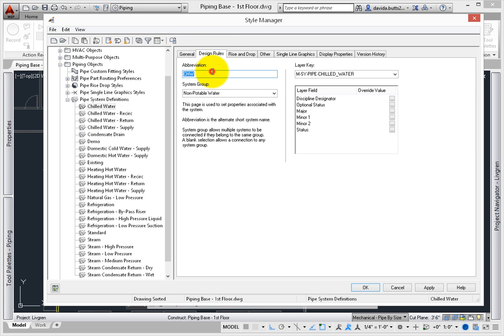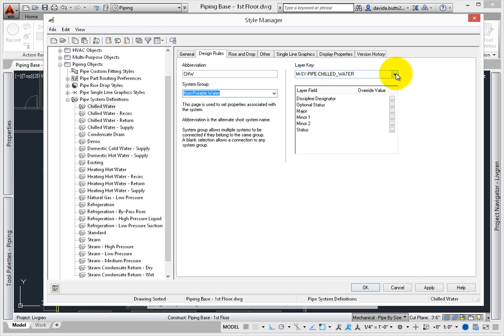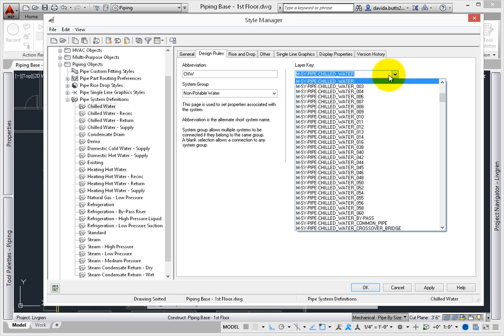Design rules set the abbreviation and system group. The system group prevents items from dissimilar systems from being connected together. Design rules also includes one of the more important settings – the layer. Autodesk uses an alias known as a layer key, which is linked to a database. While this section does not go into detail about editing system definitions, know that this alias will help you comply with the national CAD standard.